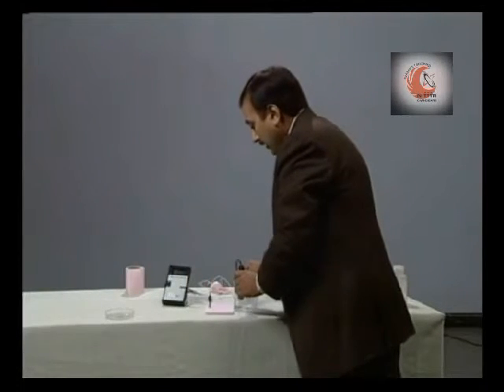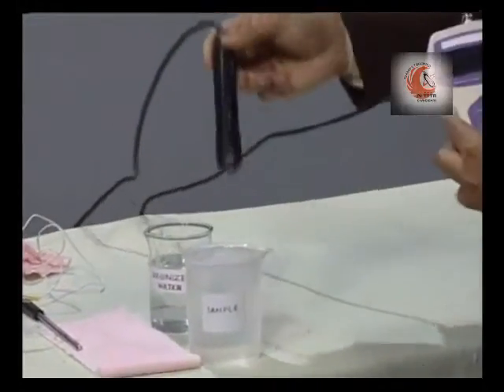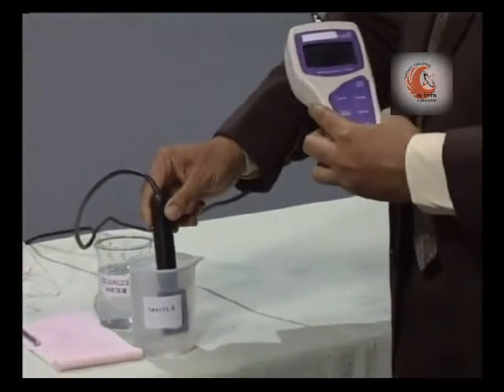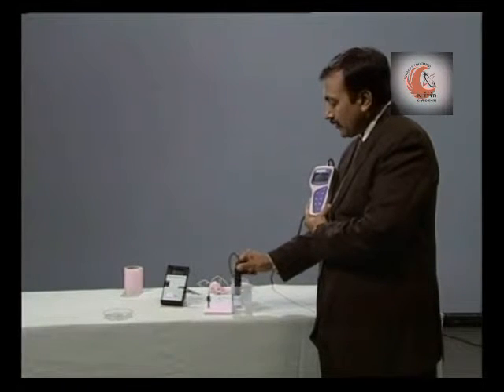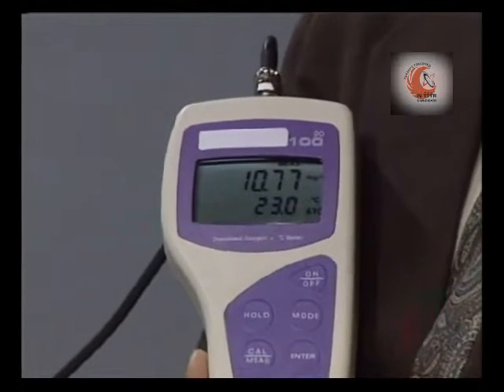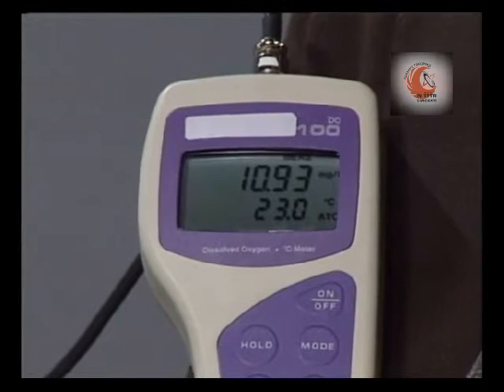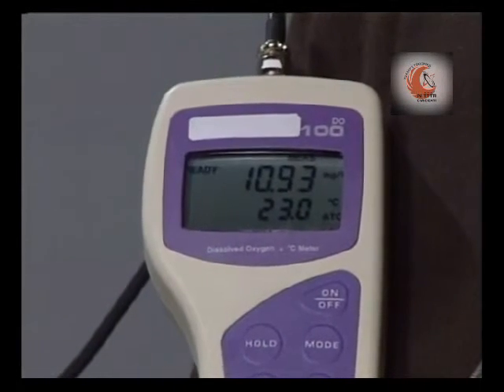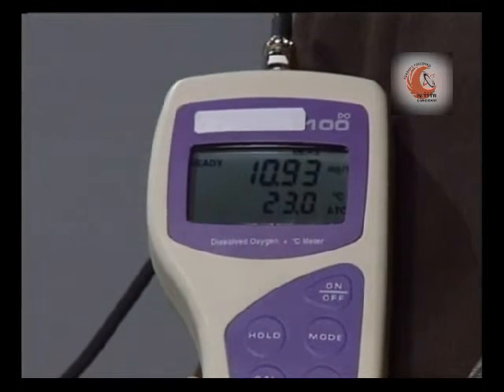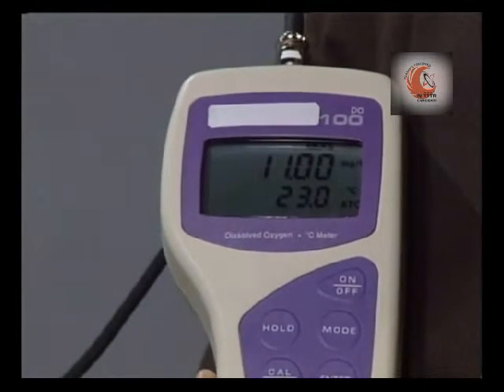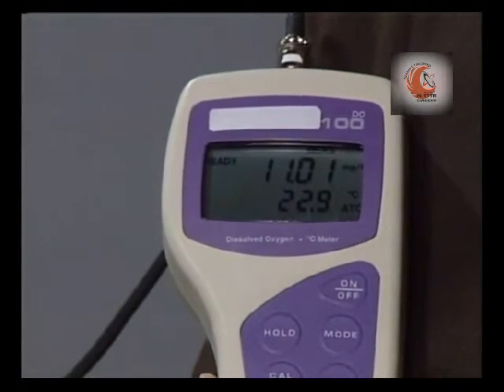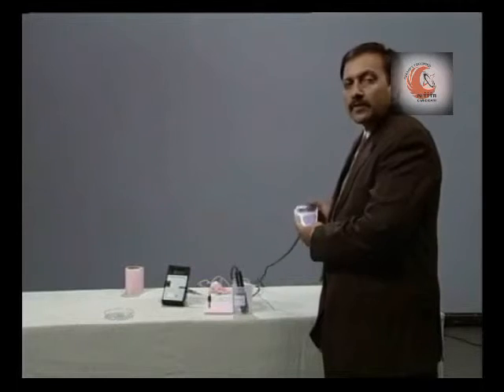So simply put the electrode into the sample and check that the instrument is in measurement mode. Gently stir the electrode and when the reading is stable, we shall note down that value. So, the ready annunciator is displayed against a value of 11.01. So, we can say that the dissolved oxygen of this sample is 11.01. Now, with this instrument you can also measure the dissolved oxygen of other water sources, for example a canal or a flowing stream or river or any other source.